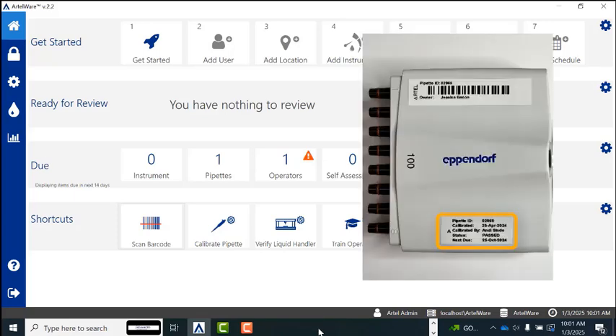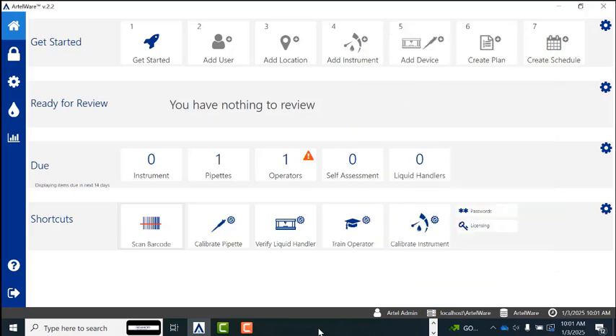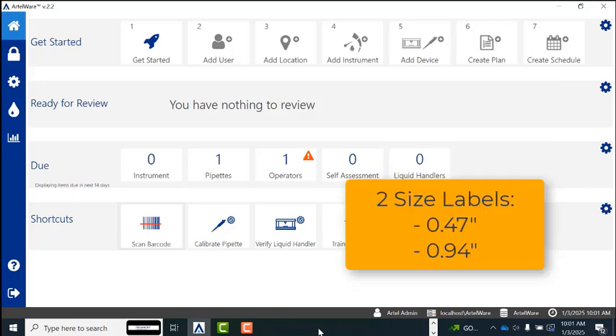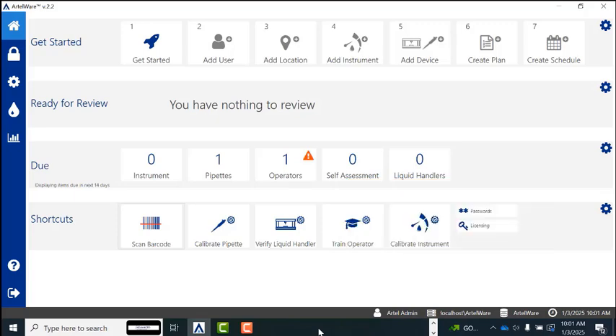In addition, you can also generate a pipette calibration label or an ALH verification label once the calibration or verification has an approved and reviewed status. There are two different size labels that ArtelWare can generate. The first size is a 0.47-inch cassette. That's used for most pipettes. There's also a 0.94-inch cassette that can be used for larger devices like multi-channel pipettes or automated liquid handlers. Today, I'm going to add the 0.47-inch cassette as most of our customers use that size label.